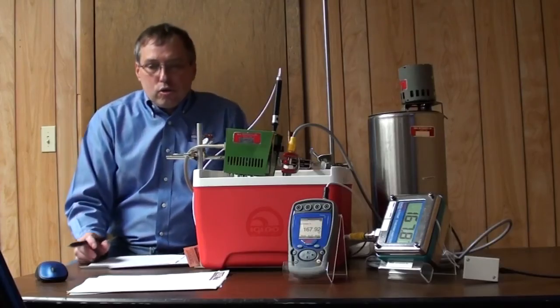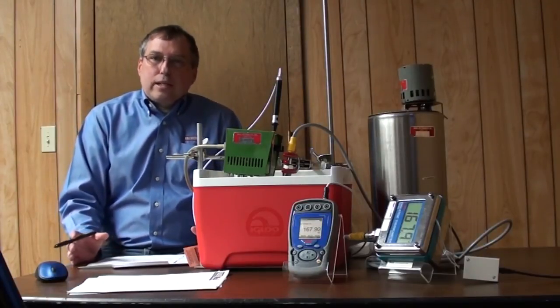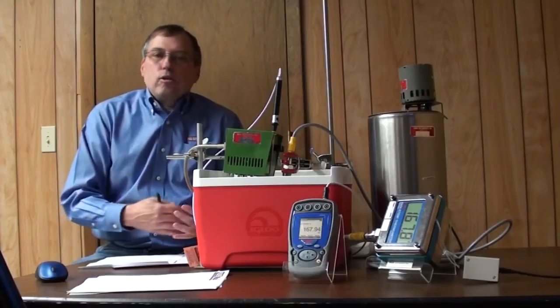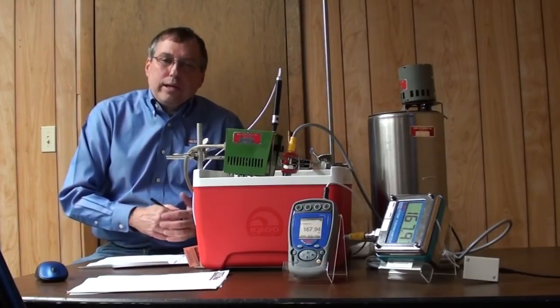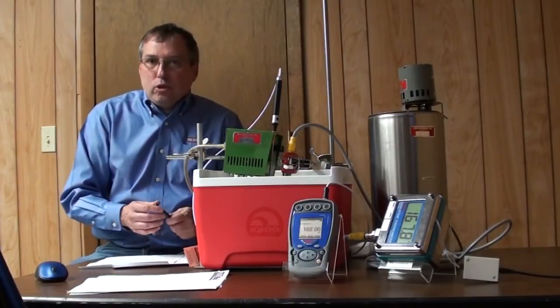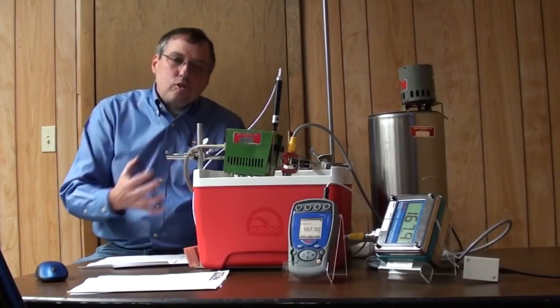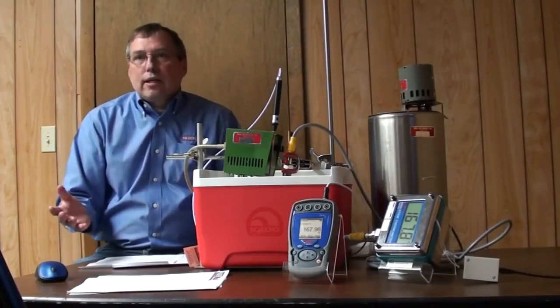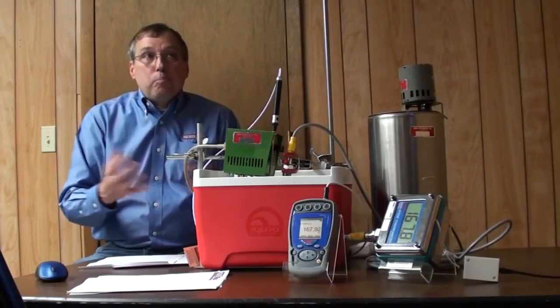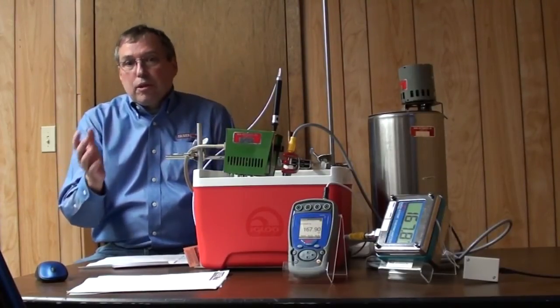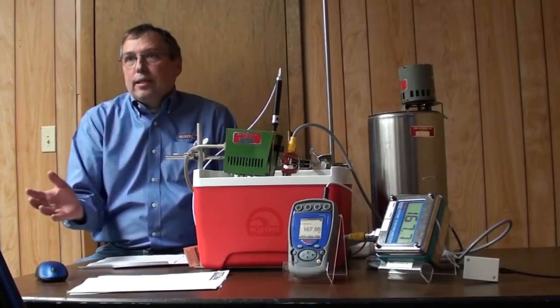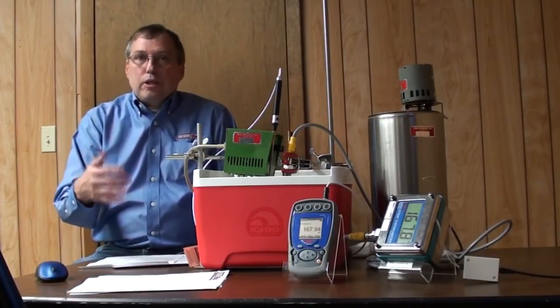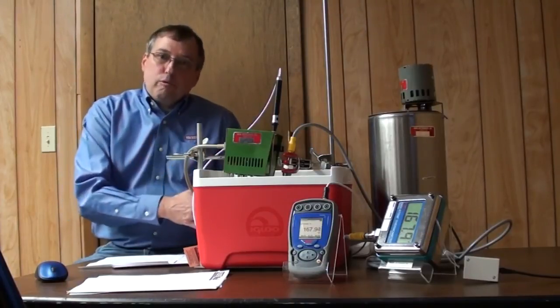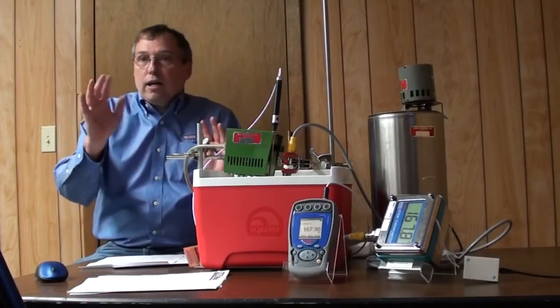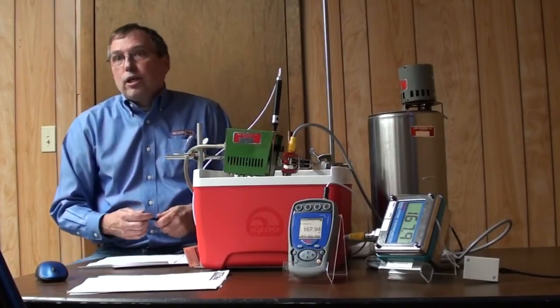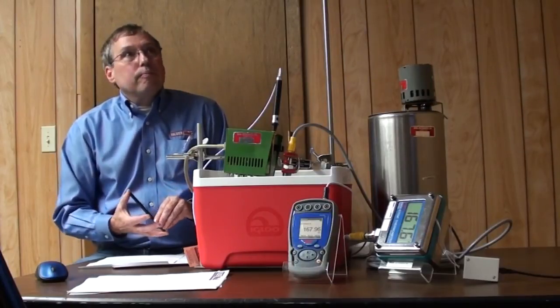Well, I used that on ours because our unit is spec'd at 0.3, and these things only have 1/10 of a degree resolution. Normally we have, for more precise instruments, an equation we use, but you wouldn't want to cut it down with this instrument. You wouldn't want to cut it in half or anything like that. There really isn't much drift. It's possible that you as the processor, remember the FDA allows 1 degree accuracy on this thing. So it's possible that you could say, well, we're okay with it being 0.3 before data and after data, or even 0.5, and that's up to your quality department and what your needs are to fit your processes. Hope that answers it.